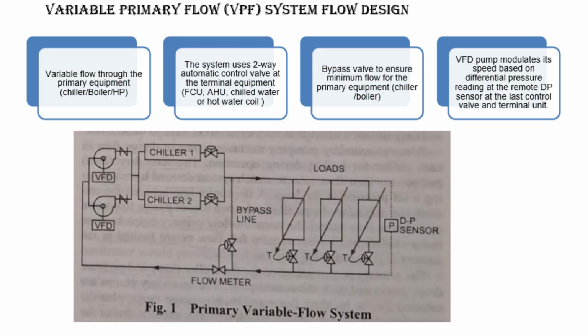These valves open and close in response to the zone load, controlling how much chilled or hot water flows through the coils. To protect the primary equipment, a bypass valve is included. This valve ensures that a minimum flow is always maintained through the chiller or boiler, even when most of the terminal valves are closed. A differential pressure sensor is typically installed at the farthest terminal unit.